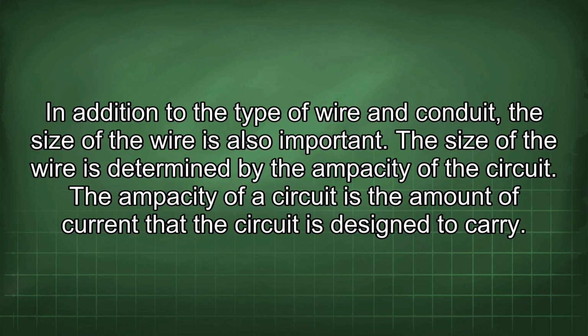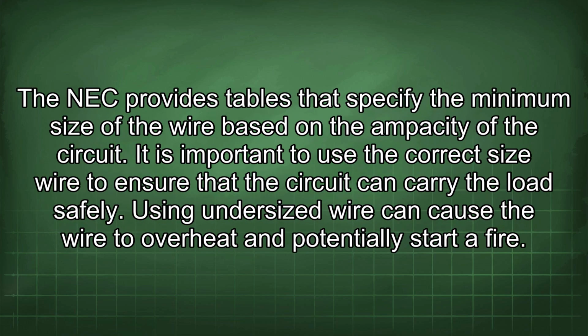In addition to the type of wire and conduit, the size of the wire is also important. The size of the wire is determined by the ampacity of the circuit. The ampacity of a circuit is the amount of current that a circuit is designed to carry. The NEC provides tables that specify the minimum size of the wire based on the ampacity of the circuit. It is important to use the correct size wire to ensure that the circuit can carry the load safely. Using undersized wire can cause the wire to overheat and potentially start a fire.